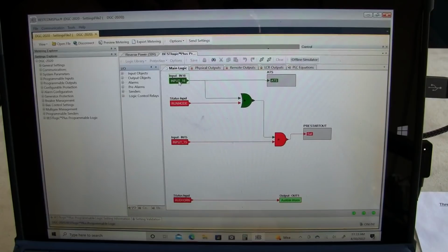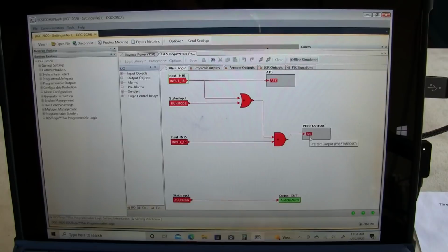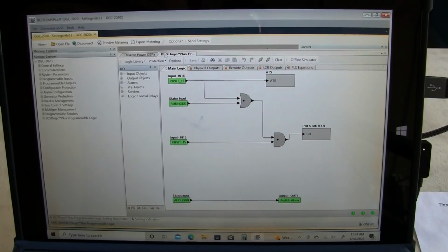So that's extremely basic. I'd like to refine this a little bit. I'd like to be able to remove that 5-second time delay on crank when we are not using the pre-start. That's a whole other thing I got to go into, but this works fine for now. So that's pretty much it. Let's see, turn that off. All right, well, that was an extremely basic overview of what you can do with these controllers. But I really like these. They're really easy to work with. So I think at this point, we're ready to haul this thing outside, hook the load bank up, and do our commissioning load bank, 4 hours at 100%. So let's get to it.